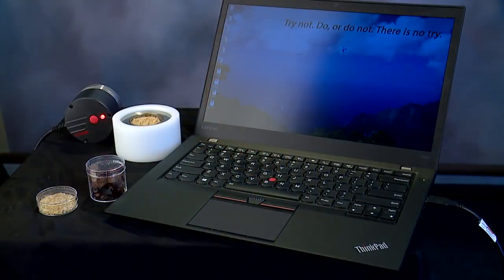For the AW Therm, this will be the test temperature, while for all the other instruments, the sample material should be at the same temperature as the instrument. Running a water activity test from your PC is quite simple.